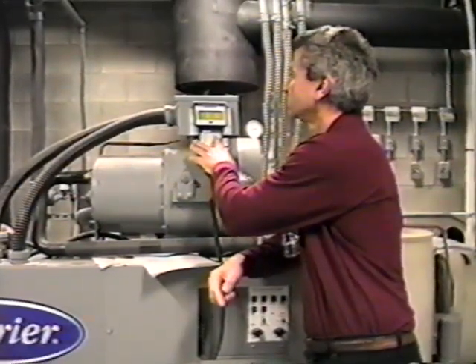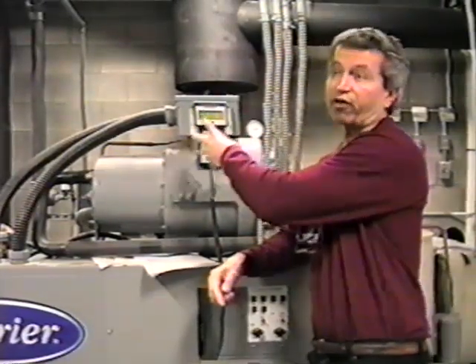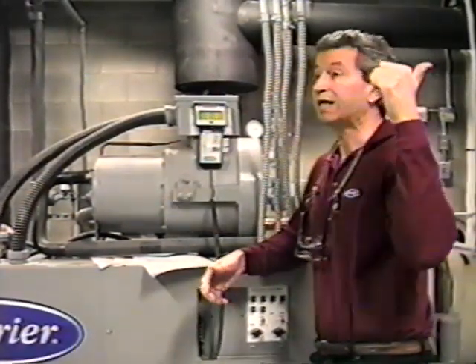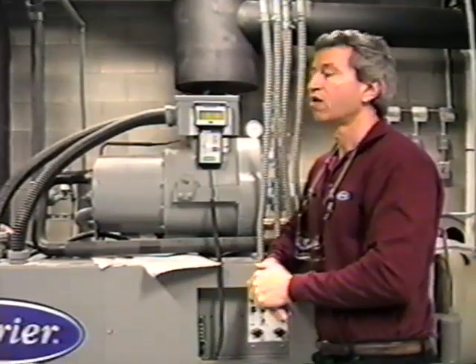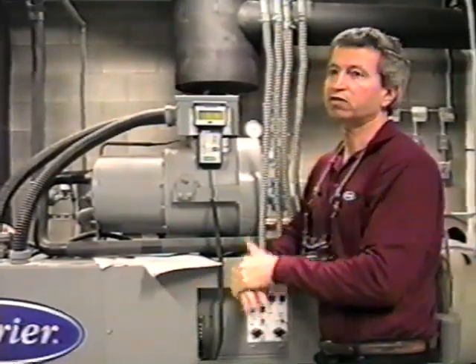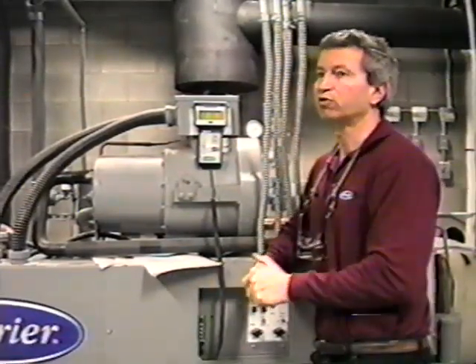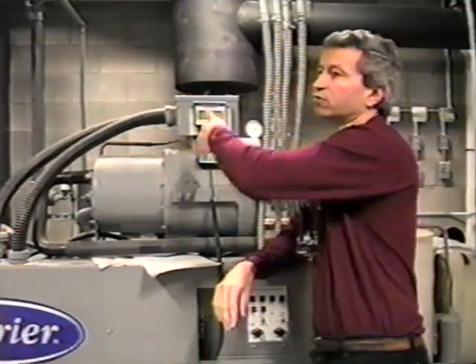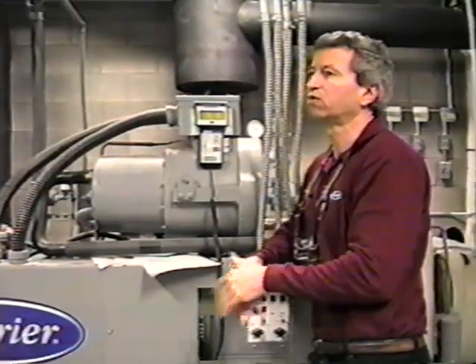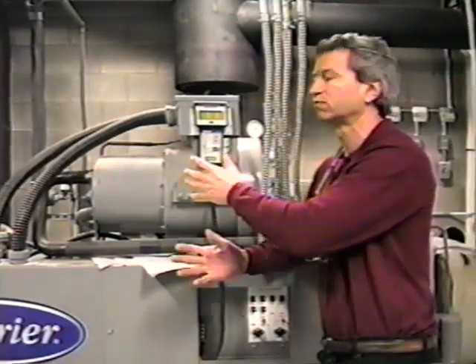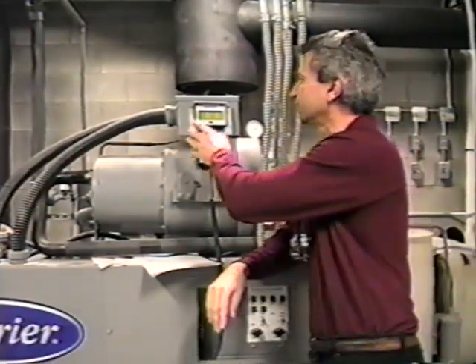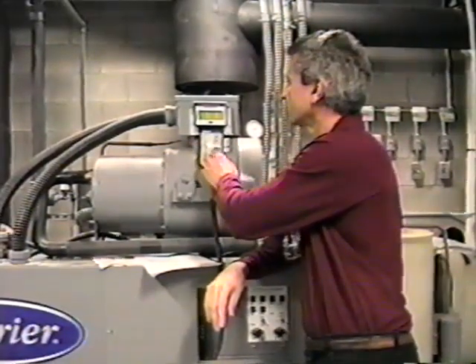Fans, because this is a generic control for, like I said, an air-cooled package machine, this processor has capabilities of cycling those fans on that air-cooled machine on and off. So you see some items sometimes on the screens that don't pertain to your particular machine. Don't let that confuse you. These just aren't being utilized at all.